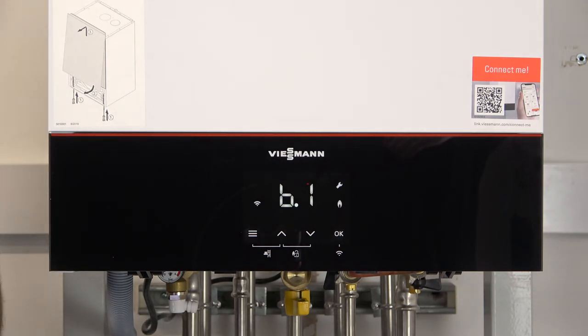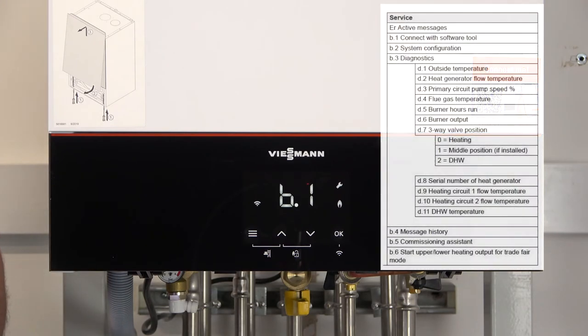You can see there the first code that comes up is B1, and for a full list of all the codes we look at the manufacturing instructions. I will put a screen in shot for you so you can see as we go through this video today what it means when I'm going through the codes. B1 is for connecting with the software tool. That's more for our service engineers when they're on a warranty call to get access into the boiler with their systems.